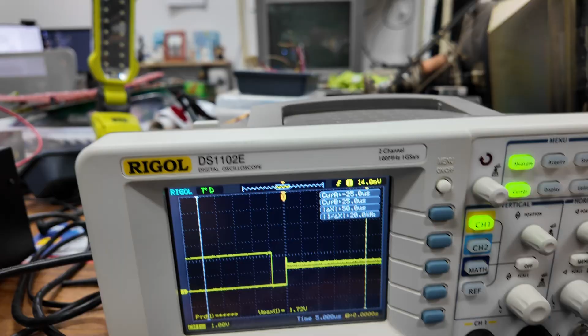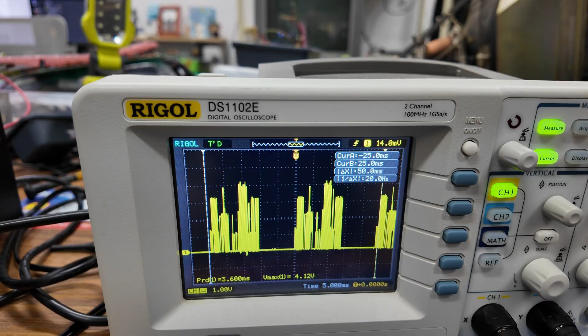If we change the scale to, say, 5 milliseconds, we can see this is showing roughly each refresh cycle in the monitor. This tells us that the voltage coming from the main boards, like the vector generator, is putting out roughly the right signal, because we're hitting 4 volts here pretty regularly. So the signal from the board looks good, and I don't think that's a problem. We've ruled that out.